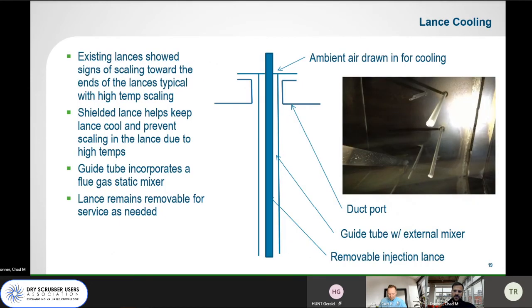Also, the original lances they had were not shielded. It's basically a pipe carrying hydrated lime stuck in a high temperature 700-degree duct. So by the time the hydrated lime gets to the bottom of that lance, it gets hot and starts to scale. So everywhere else we've implemented these shielded lances that basically pull in ambient air around the pipe actually conveying the lime, which gives a cooling effect, which helps to prevent scaling and pluggage of those lances.